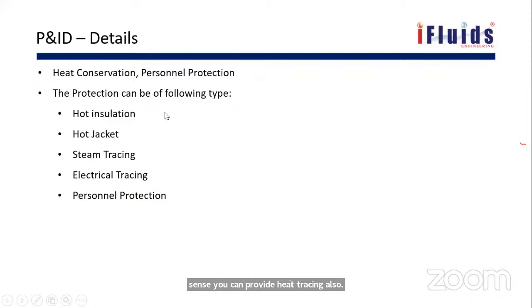In some other cases, we may have cold conditions, like winter, night, or in cold countries. If the temperature is susceptible to going low, or during shutdown there may be some open portion, where they open the vessel or open some insulation, it will be left unattended and remain open during operation. To avoid that, they will provide steam tracing to maintain the temperature so that the process temperature does not go below the lower value. If it does, it may go for solidification. So they need compulsory heat tracing, which may be steam tracing or heat tracing through an electric heating system.